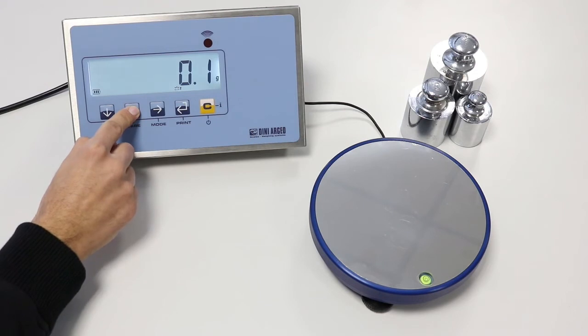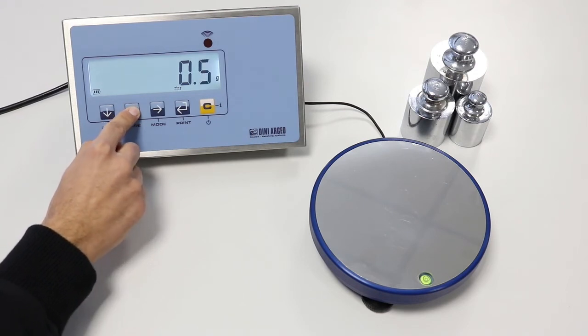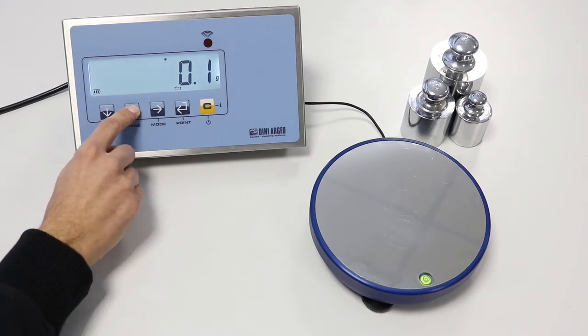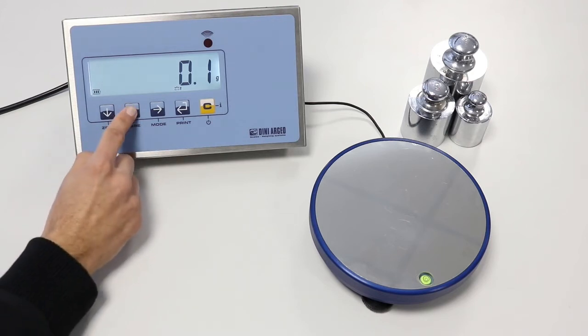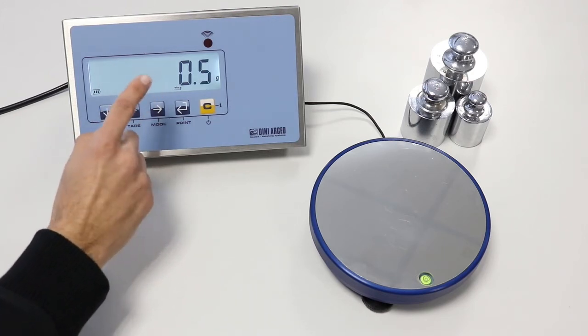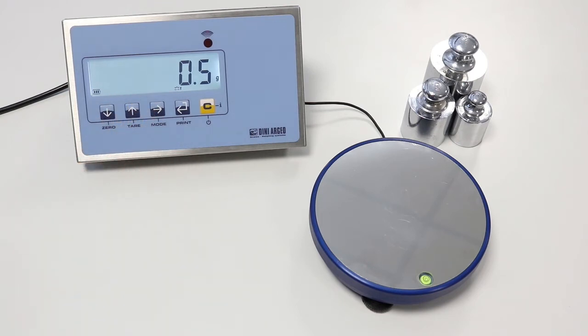Next step is DIV, the minimum division of the scale. Using TARE, you scroll through possible settings. For multi-range scales, we set the division of the first range, then the division of the next ranges will be set automatically. For our example, we set 0.5 grams for the first range, so automatically the division of the second range will be 1 gram.